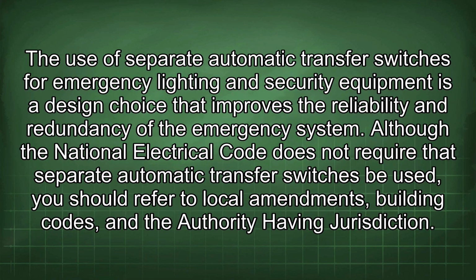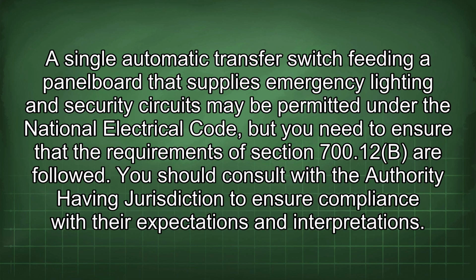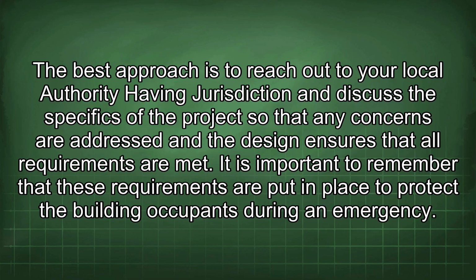for emergency systems. The use of separate automatic transfer switches for emergency lighting and security equipment is a design choice that improves the reliability and redundancy of the emergency system. Although the National Electrical Code does not require that separate automatic transfer switches be used, you should refer to local amendments, building codes, and the authority having jurisdiction. A single automatic transfer switch feeding a panel board that supplies emergency lighting and security circuits may be permitted under the National Electrical Code, but you need to ensure that the requirements of Section 700.12b are followed. You should consult with the authority having jurisdiction to ensure compliance with their expectations and interpretations. The best approach is to reach out to your local authority having jurisdiction and discuss the specifics of the project so that any concerns are addressed and the design ensures that all requirements are met.